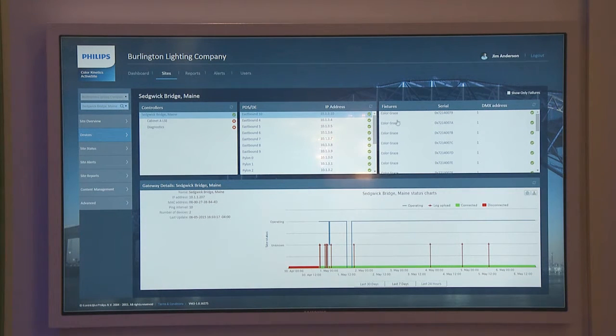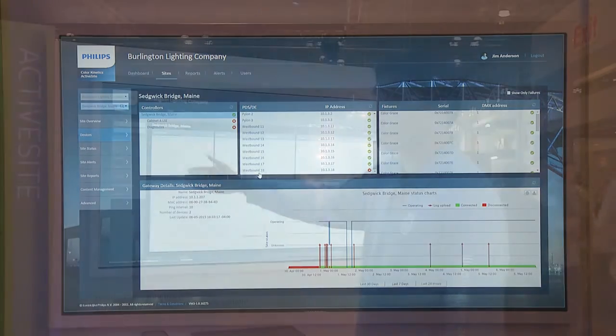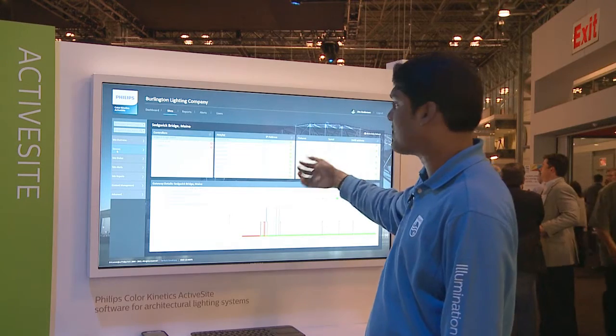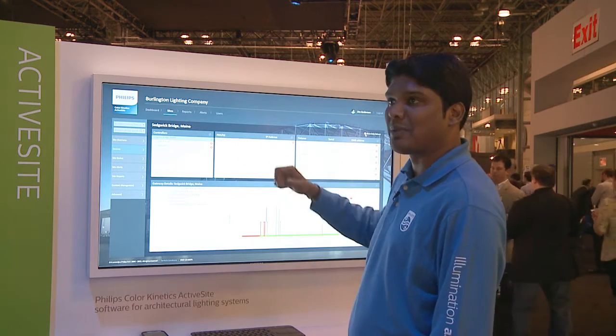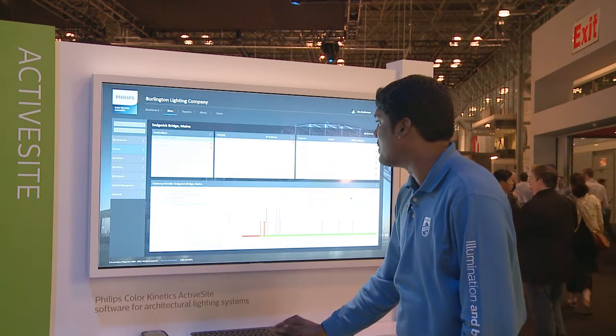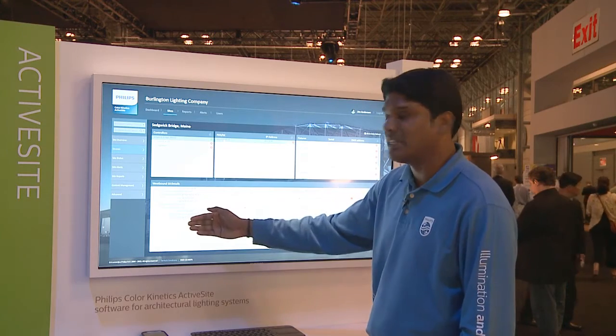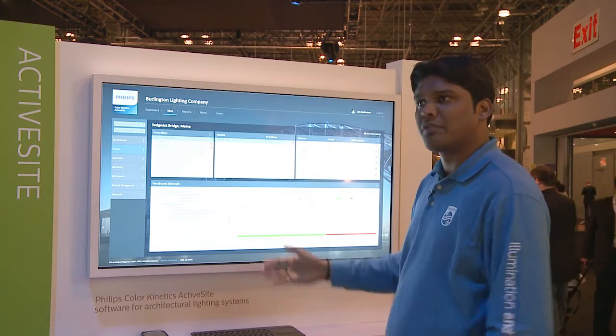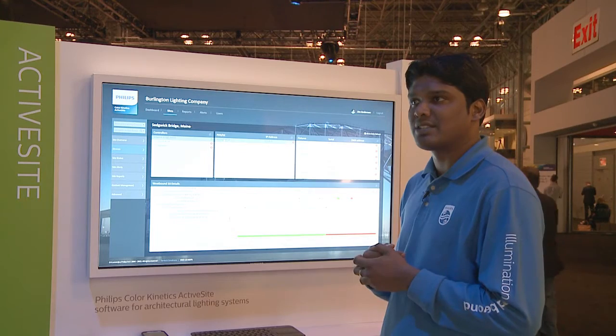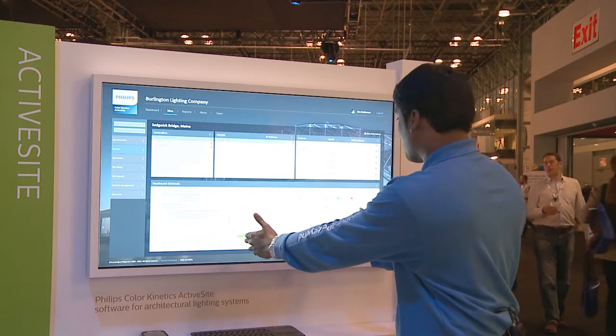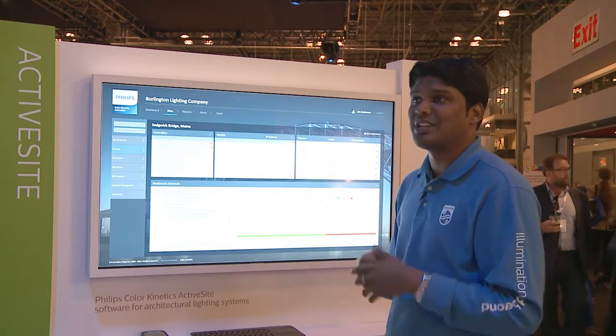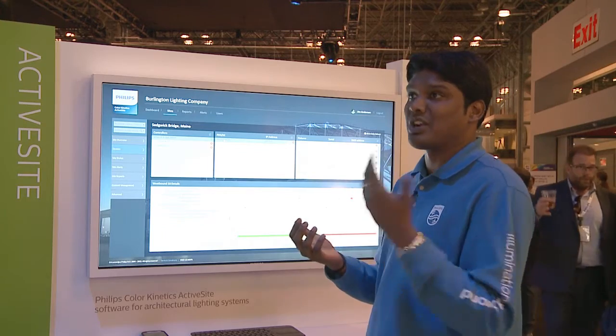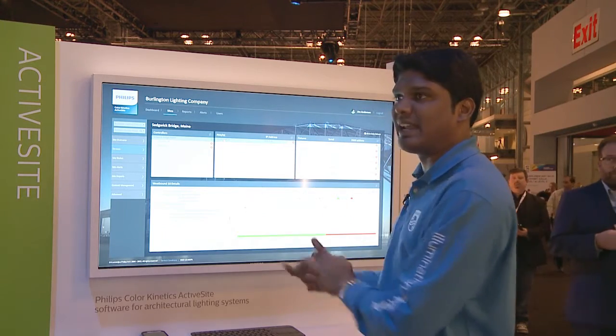To see what those alerts are, I go in here. It's set up so you can see the controllers, the power supplies, and the fixtures, and you can see exactly what's gone bad. This power supply has gone bad — it tells me exactly when it went bad. I can see all its properties and view the performance graph over time. You can see this power supply was working fine until the third of May and then it stopped working. Before ActiveSite, if you didn't go on site to do monitoring, you'd have no historic analysis. Now you get all of this with charts and data analytics.